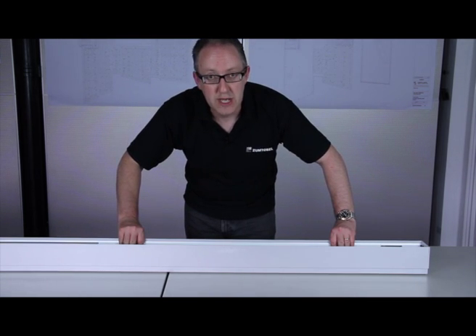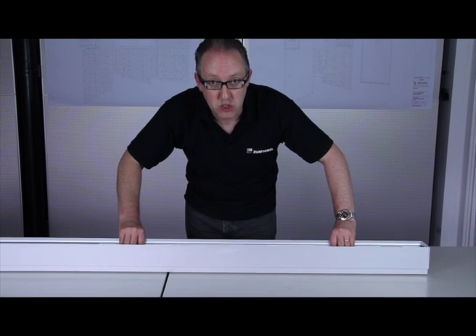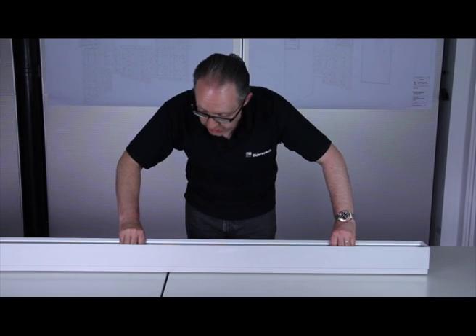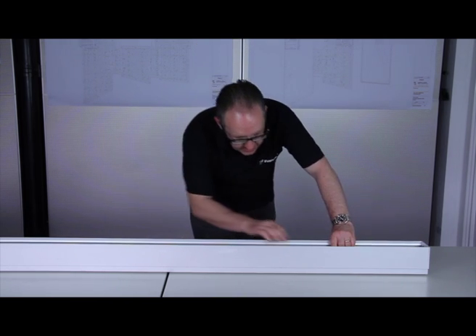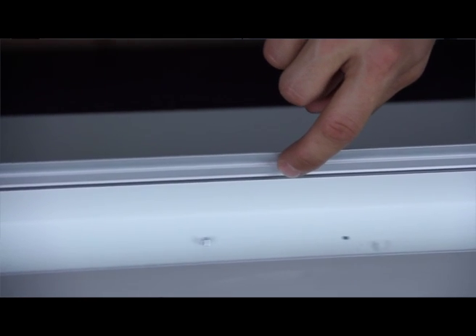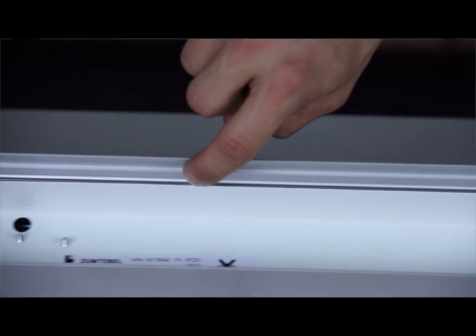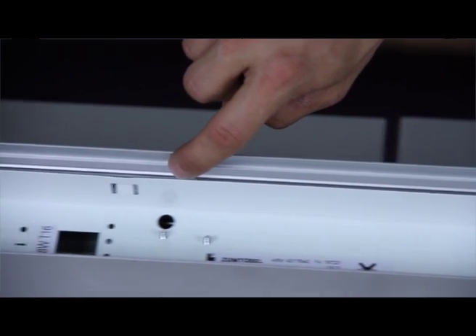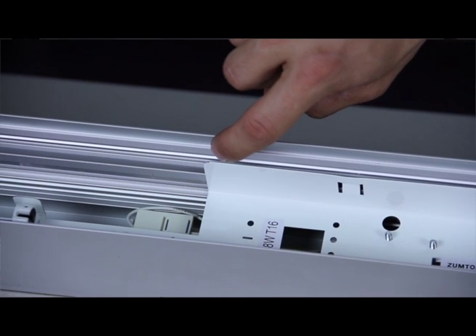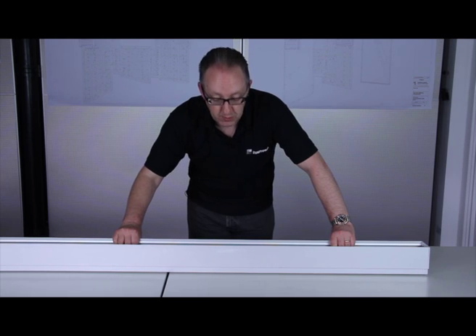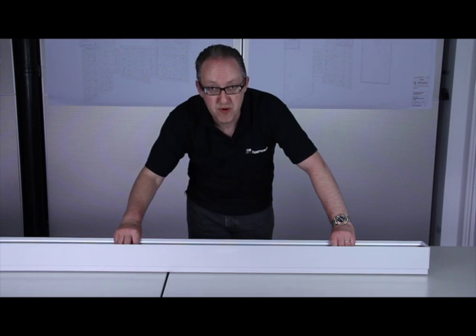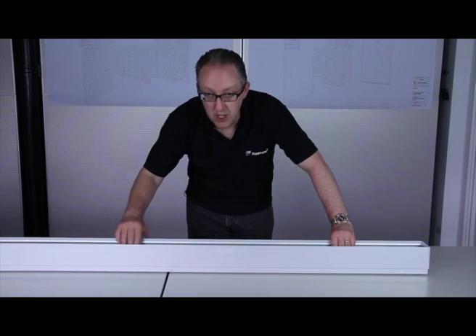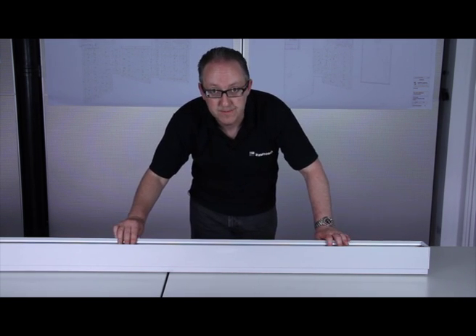Then the gear tray, checking to make sure there are no wires trapped, needs to be offered into the extrusion and then clicked in. It's critically important to make sure it's clicked in twice. Two clicks, and then make a visual check to ensure that the edge of the gear tray is parallel to one of the lines in the extrusion. That will ensure the gear tray is properly clicked into place at all four positions.